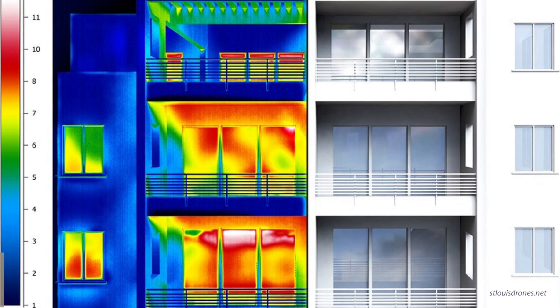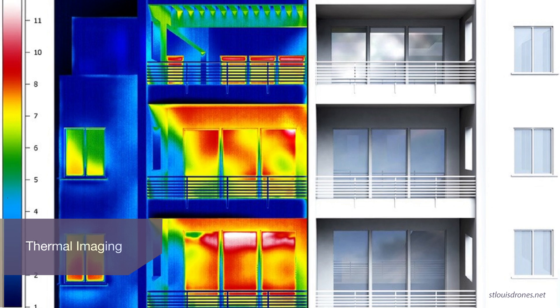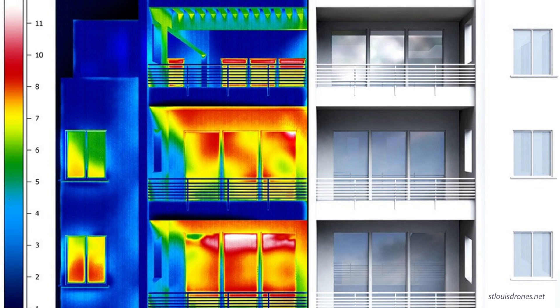After air tightness and insulation have been taken to an appropriate level, thermal bridging losses can account for as much as 30% of all losses for the entire building. The biggest challenge in this space is windows and doors. However, good quality design can bring that figure to less than 10%. In these cases, the use of a thermal break element must be included to minimize loss.